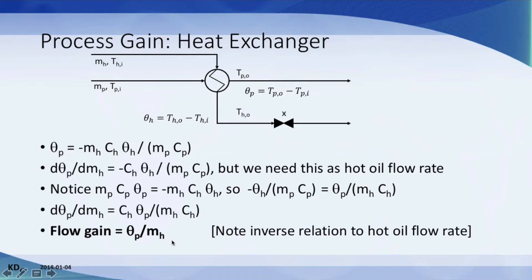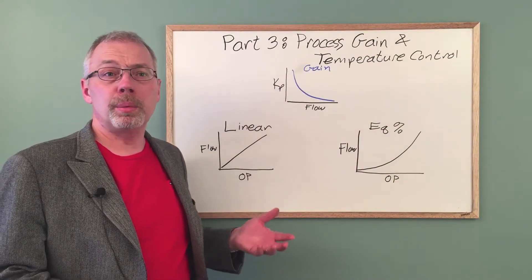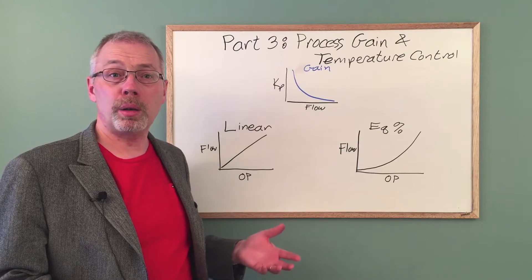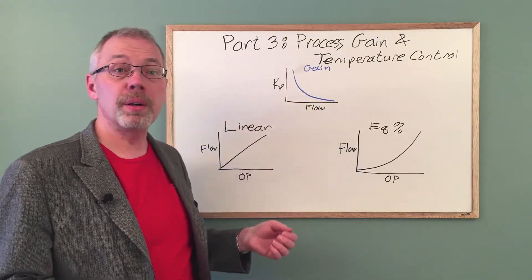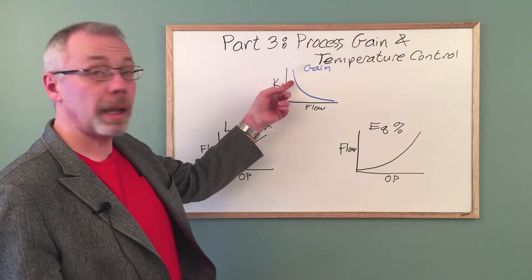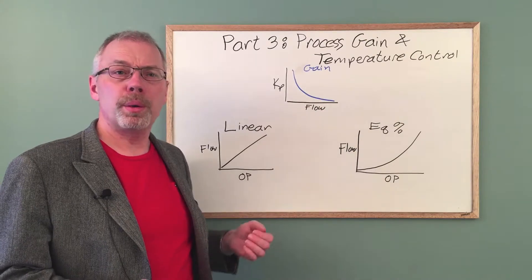Note that the flow gain is inversely related to the hot oil flow rate. Graphically, the relation between the flow gain and hot oil flow rate is shown here. There is a high flow gain at low flow rate and a low gain at high flow rate.